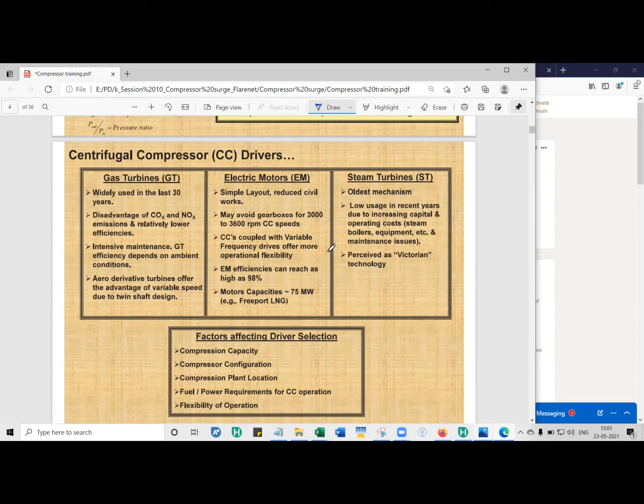You can hit pretty high power ratings with steam turbines. However, if you wish to use a steam turbine to drive a centrifugal compressor, first you need a source of water, a water treatment facility, a polishing unit to the given specification. You can have scaling issues if water is not treated properly, safety issues such as boiler explosions or tube ruptures. And steam, to generate steam, you need fuel, and fuel costs money.